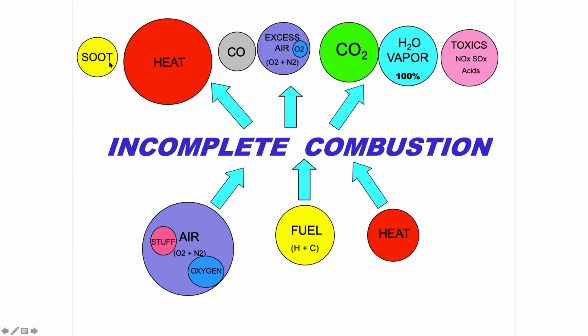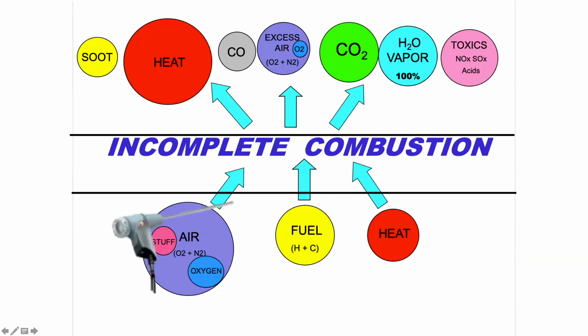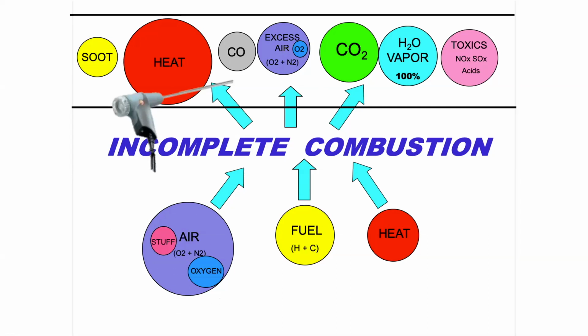So this gets into the more complex analysis of what can happen in a combustion situation. And what I've done here now is added the stack. It's laying horizontally, but this is your stack. And this is what the combustion analyzer probe actually measures. So you can make inferences from how combustion is operating from what you measure on the output side. That's what your combustion analyzer does, it measures the temperature and the constituents, the elements that are in the air, and does some calculations to tell you what's going on.